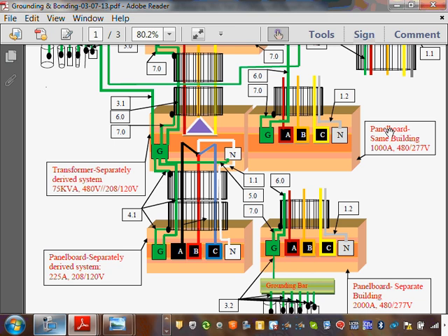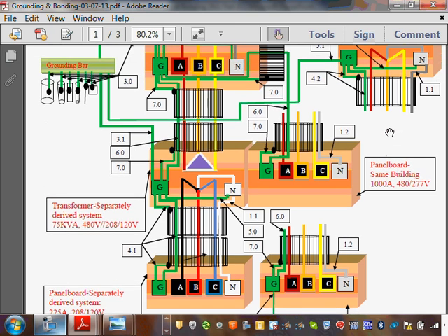So now let's take another feeder and feed the so-called separately derived system. Now I took a feeder from the same switch here to a transformer that I own, operate, and install, not a utility. Typically, from this transformer, I dump the power into another panel at a different voltage.